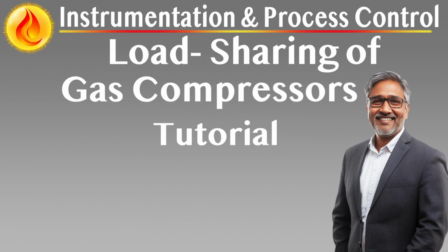Operational advantages. Early surge intervention mitigates surge risks proactively before reaching compressor-specific thresholds. Reduced hot recycle dependency minimizes the need for individual compressors to open their recycle valves, reducing wear and energy loss. Centralized control logic simplifies tuning and coordination compared to managing multiple independent recycle paths. Improved cooling and efficiency: it utilizes shared heat exchange infrastructure to maintain gas density and operating efficiency. Smooth capacity transitions: it offers a gentle surge relief mechanism that stabilizes the entire compressor train during prolonged turndown.